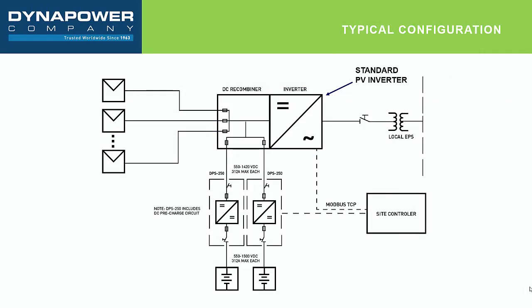So let's shift now and talk a little bit about what this might look like in more detail. This is a very typical generic diagram of what it's going to look like when you DC couple storage to an existing or a new PV array. In this particular case, we're looking at a standard PV inverter, and behind it we've got a DC recombiner. And this may or may not be required for a DC coupled system. The recombiner is only needed if the PV inverter does not have sufficient space and protection on its existing DC bus internally. Many PV inverters do have these extra lugs that can be used for DC coupling, in which case this DC recombiner is in fact not needed.